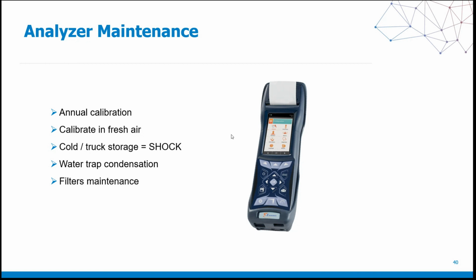So you might not know that there's already 100 ppm of CO inside that space if you turn it on inside. If you turn it on outside, like I have instructed you to do, as soon as you enter the space, you're going to see that 100 ppm show up right away in your display. You're going to know to shut the system down, open the windows, evacuate the occupants, and everything else that's going to follow suit after that.